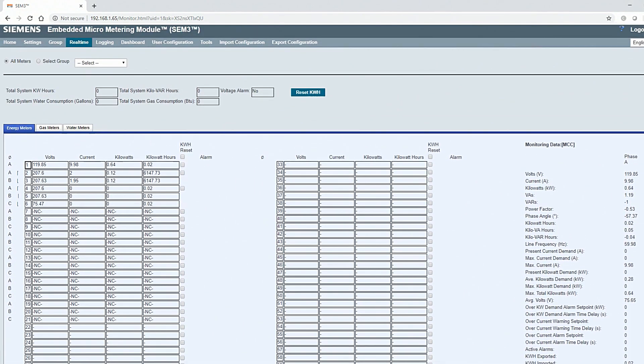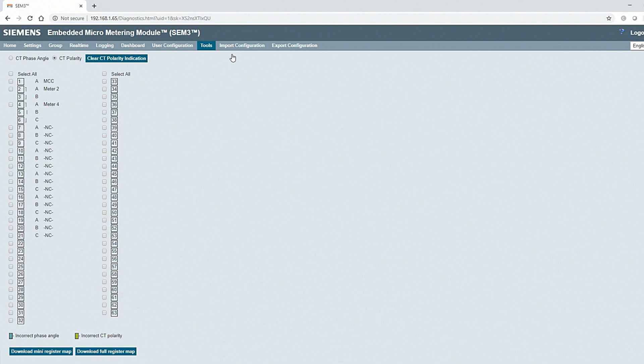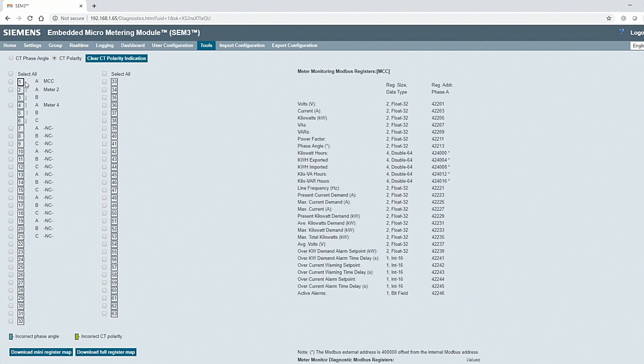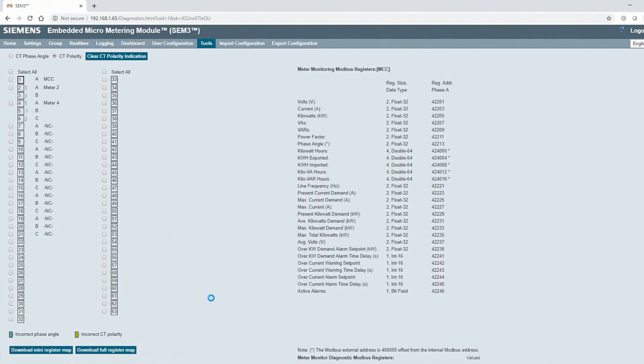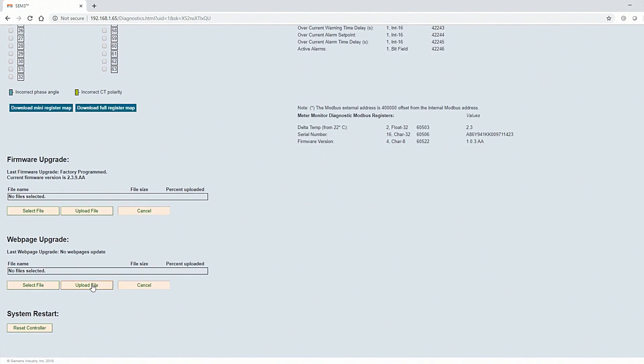You can access diagnostics by selecting Tools and Diagnostics. With this tool, you can verify CT direction, meter module dip switch selection, provide Modbus addresses for third-party software integration, download the Modbus device map, and perform firmware updates.